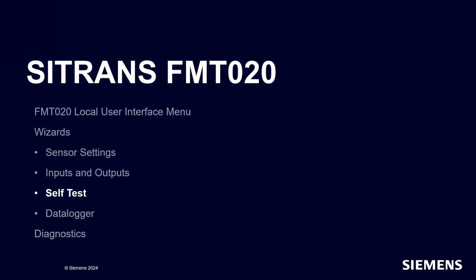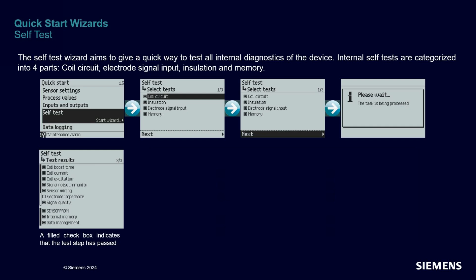Let's have a brief look at the self-test wizard. Self-verification is a powerful tool that allows customers to maintain complete confidence in the performance of the installation. It is part of the three-layer strategy, a foundation of the IQ Guard concept. The first layer is the 100-plus parameters continuously checked in the background. The second layer is this self-test, which you may trigger at your convenience. It is not meant to replace the external verification offered by the SITRANS Verificator, but rather complement it. The external verification is the third layer.